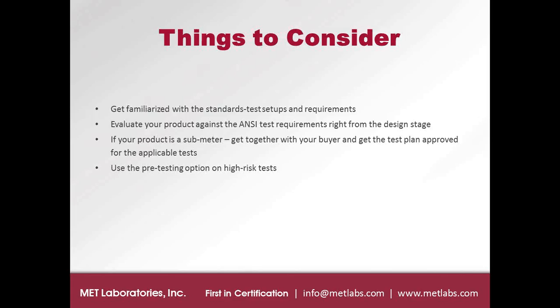Evaluate your product against ANSI test requirements right from the design stage, because there are these unusual tests, the magnetic field test and the current ground surge test, that you may not have come across in any other specs. If your product is a sub-meter, get together with your buyers and get the test plan approved for the applicable test. A lot of times this is a necessary step because, for example, let's say your product is a sub-meter that resides on a pole somewhere.